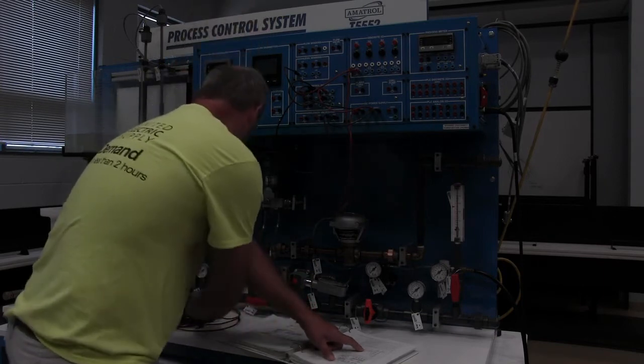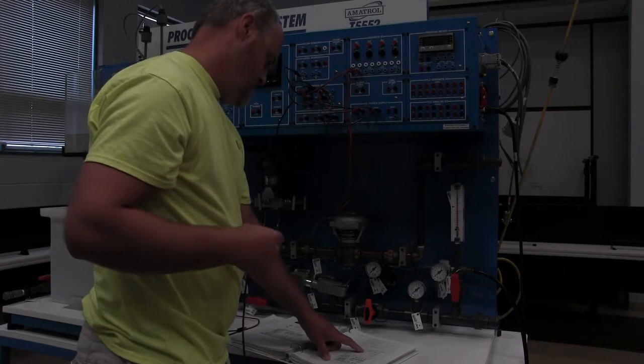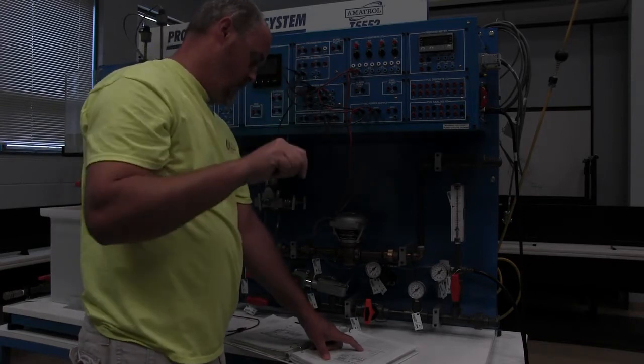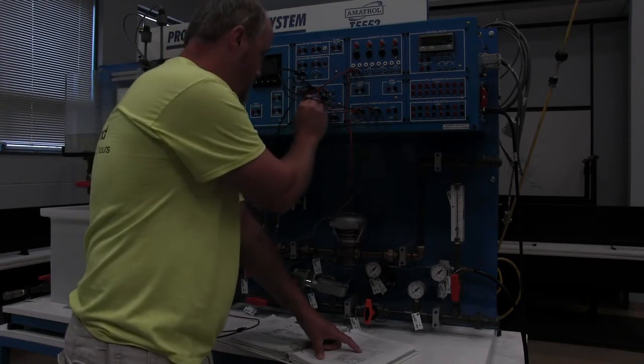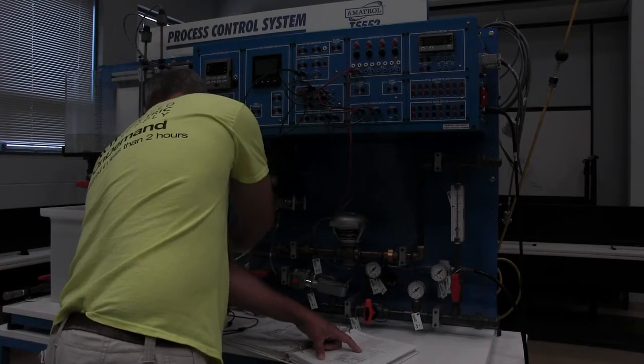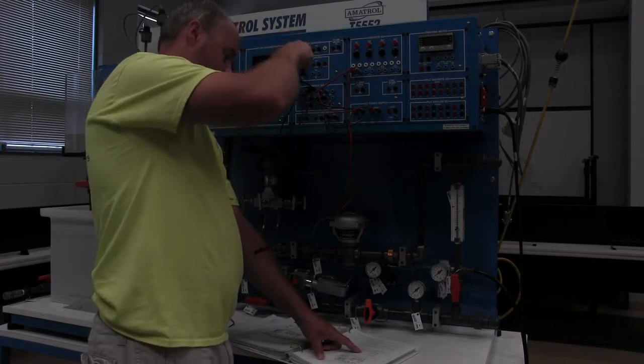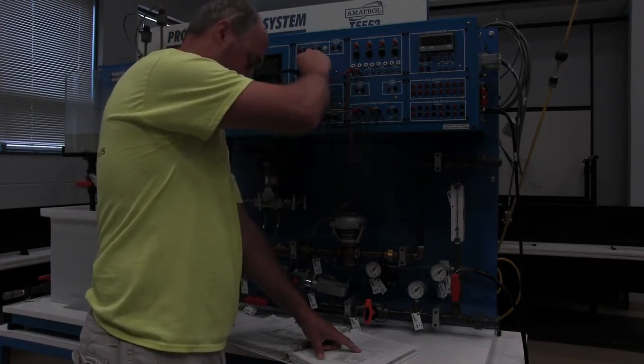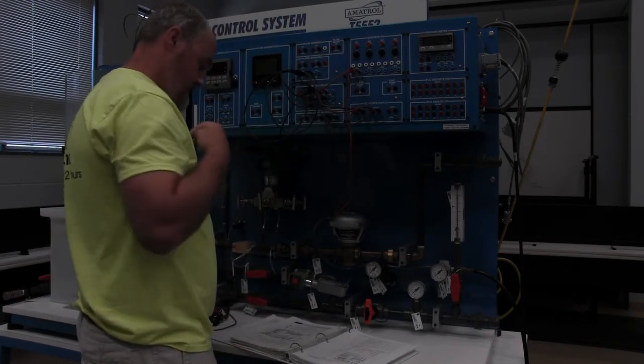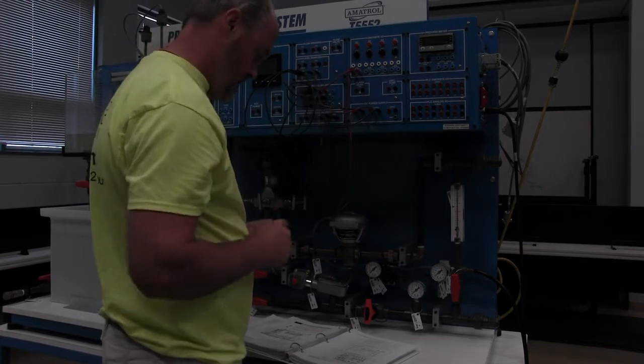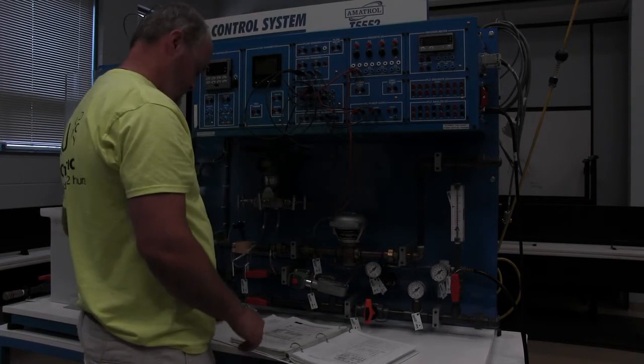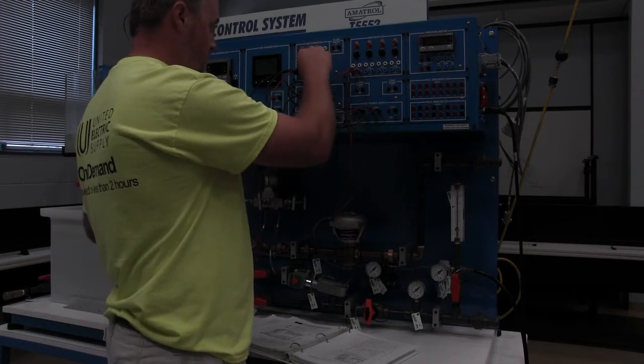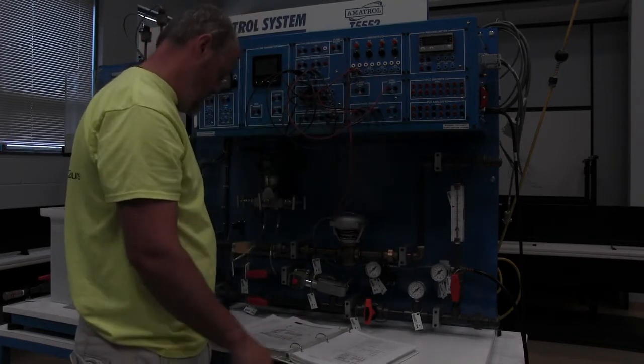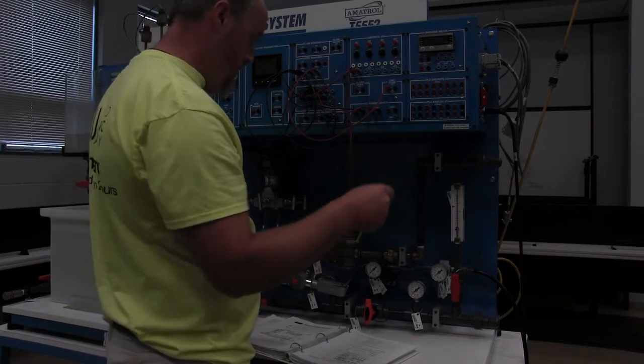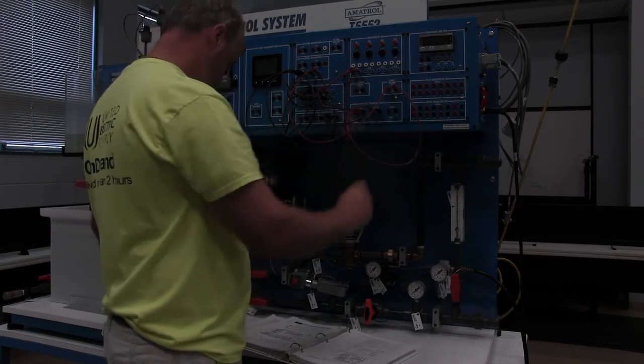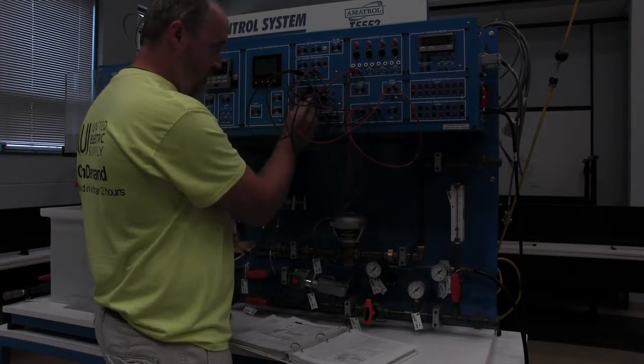From the other side of level switch 1, LS1, the opposite side of that will go to the control relay 2, opposite side, and it's also going to be going from LS1 to level switch 2, which they're using as a high level. Off of the other side of the high level, we're going to go to two places. We're going to go to control relay 2, the coil, and we are going to go to P1, which is pump 1, the positive side. And then we're going to take P1 back to a negative. And we're also going to take control relay 2's coil back to a negative.